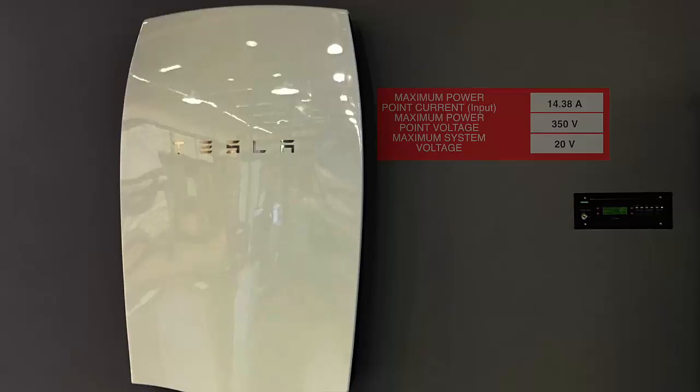Lithium-ion batteries are also becoming more popular in home installations as the price continues dropping. Most of these systems are high voltage at around 300 to 400 volts DC and present electrocution hazards. If a lithium-ion battery is overheated by either internal overcharging or internal defects, it can create a significant fire and explosion hazard. If any smoke or vapors are visible, they should be considered toxic and explosive.